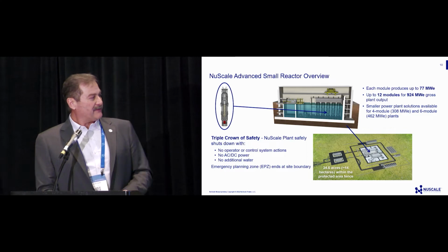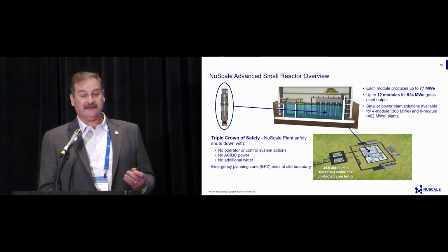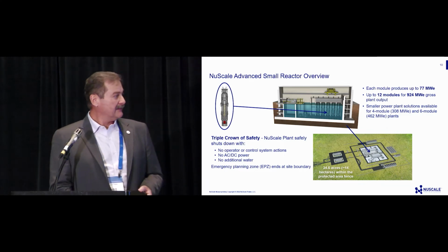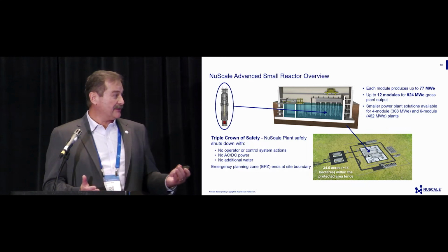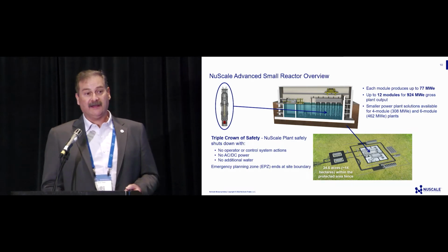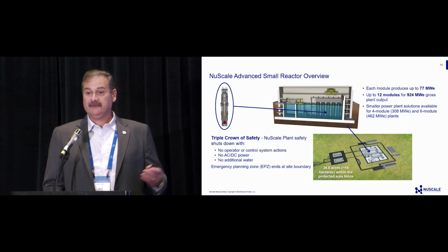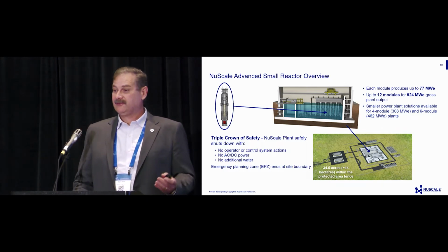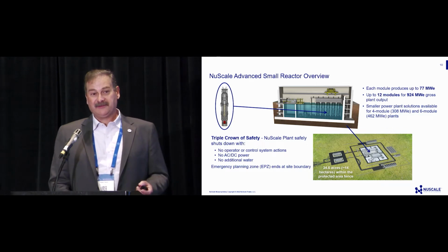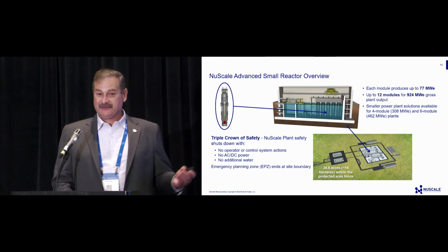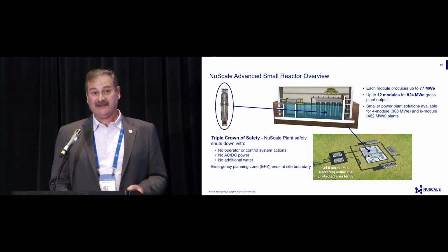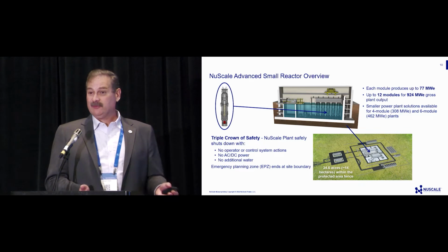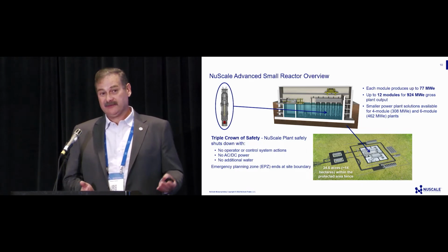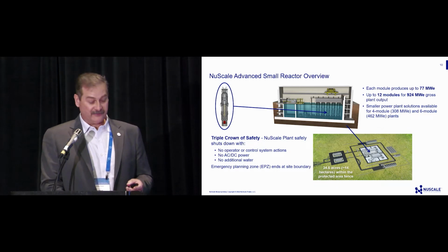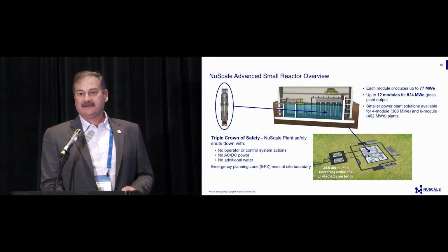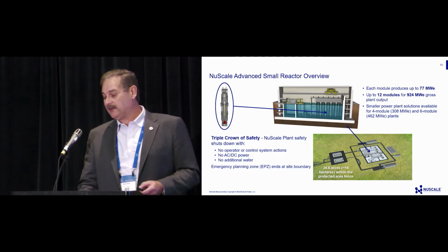So one of the things that we like to talk about is our triple crown of safety, and this is very unique to the NuScale design. There's no operator action that is required to keep the reactor safe and shut down. There's nothing the operator could do to make things worse for any accidents that we analyze for or make things better. The module can simply de-energize, lose power. It transfers over to emergency core cooling system, and it sits and rejects its heat to the pool indefinitely. As the pool water evaporates, your decay heat load drops down to a point where just air circulation will keep the reactor cool forever. So there's no required actions to have electricity. There's no safety related power requirements for the design.